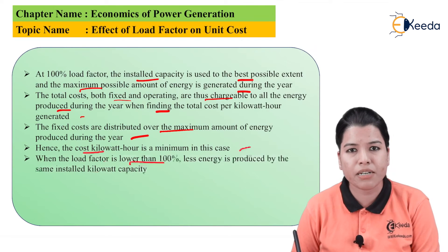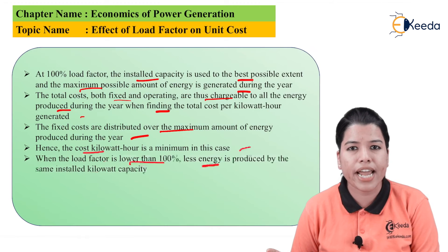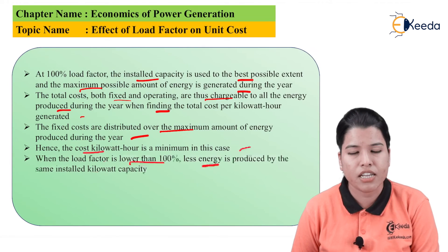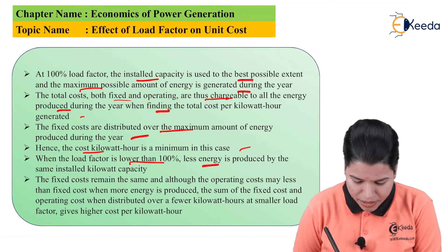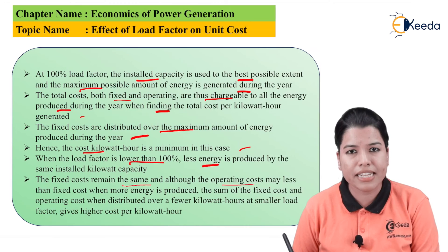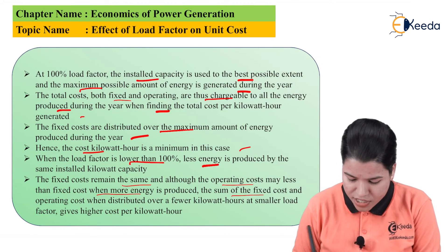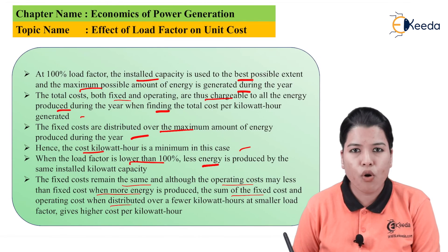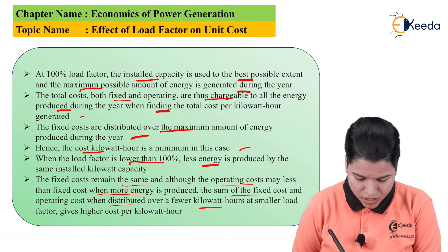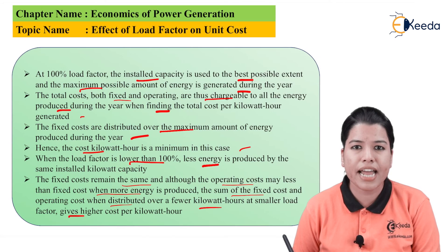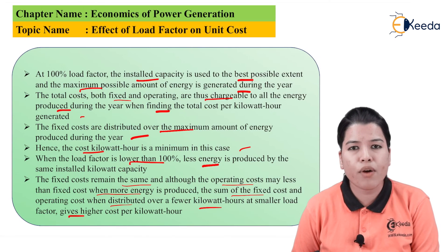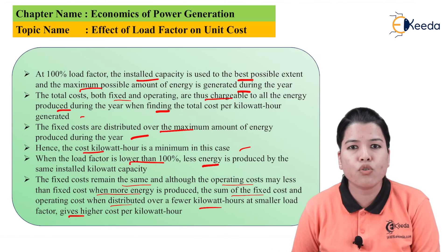Now when the load factor is lower than 100%, then less energy is produced by the same installed capacity of the plant. So as the load factor goes on decreasing, the energy which can be produced by the plant also goes on decreasing, but the cost required to produce that amount of energy goes on increasing. Fixed cost remains the same, although the operating cost may be less. Also the sum of the fixed cost and the operating cost, when distributed over the fewer kilowatt-hours, gives a higher cost per kilowatt-hour. So we can say that as the load factor goes on decreasing, the cost per kilowatt-hour goes on increasing and the generation also goes on decreasing. This is the effect of load factor on the cost of electricity.